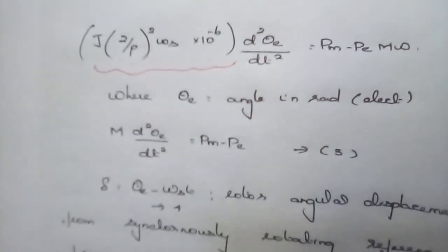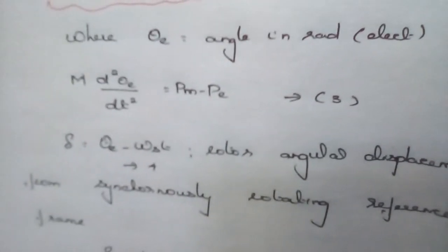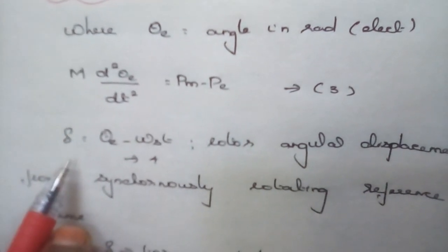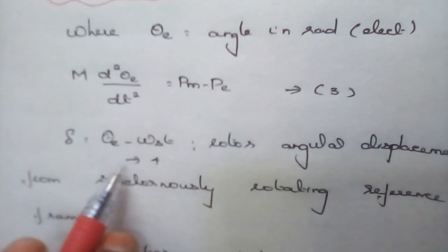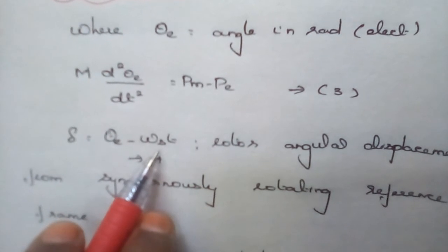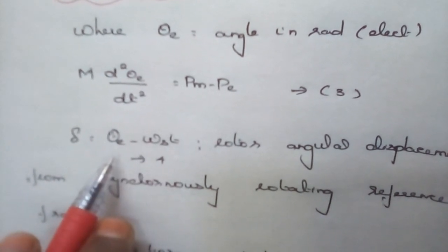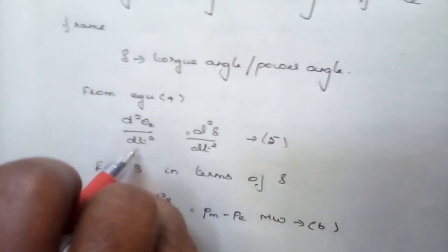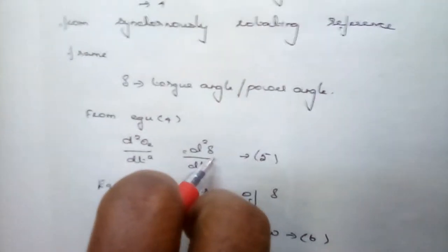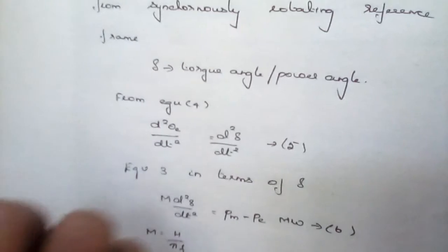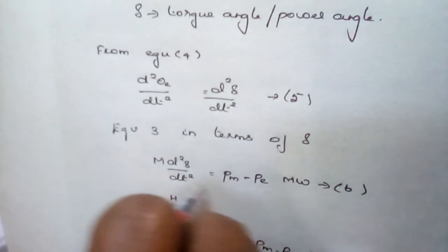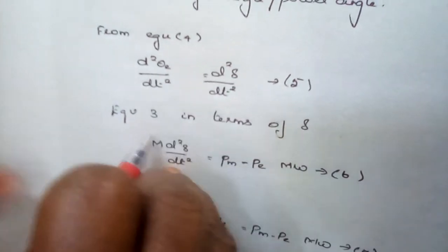M is the measure of angular position of the rotor with respect to the synchronous rotating frame. Next, we write the rotor angle displacement delta expression, given by: δ = θe − ωs·t — consider this as equation 4. Here, ωs·t represents the component running at synchronous speed, and θe is the angle in electrical radians. By differentiating equation 4 and equating, we get d²δ/dt², which is equivalent to d²θe/dt². Substituting d²θe/dt² as d²δ/dt², we get: M · d²δ/dt² = Pm − Pe in megawatts.